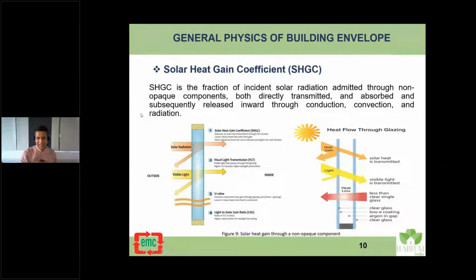What is SHGC? For the glass Ruby just selected, you will notice in the catalog they have something called SF. Now SF is the same as SHGC, which is the same as G factor - manufacturers use different terms, but mostly SHGC is less than the shading coefficient, approximately 0.87 of the shading coefficient. Whatever is the lower value is something you can take, which is the same as SHGC. Now remember, if you are shading your glass just like you shade your eyes, you can go for glass with higher SHGC, because the shade adds to the SHGC and makes it much better.